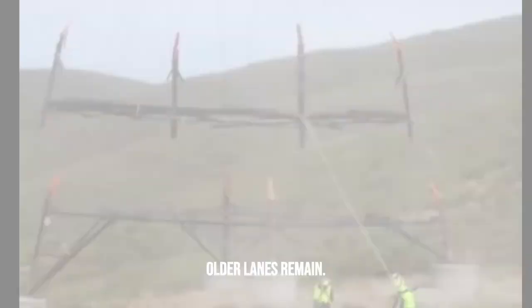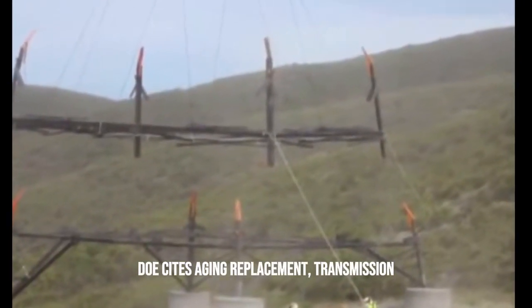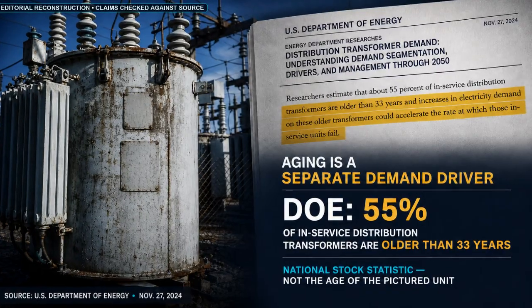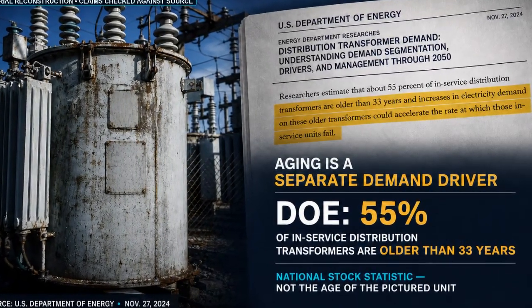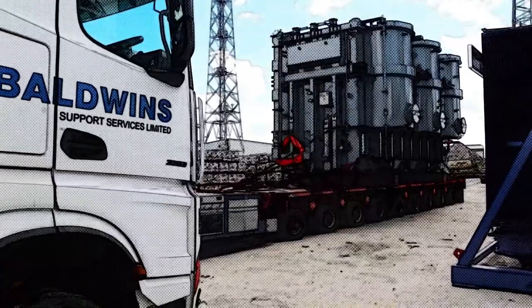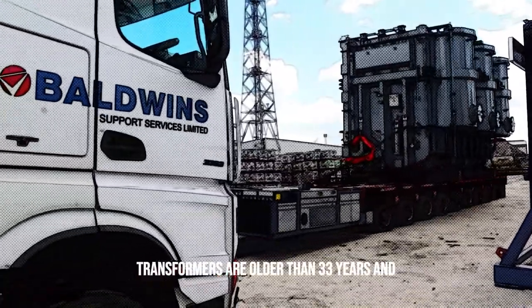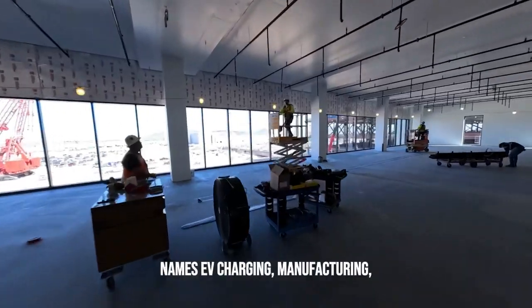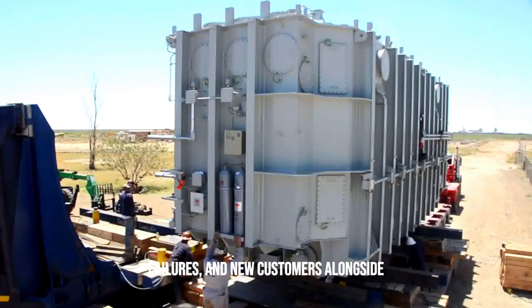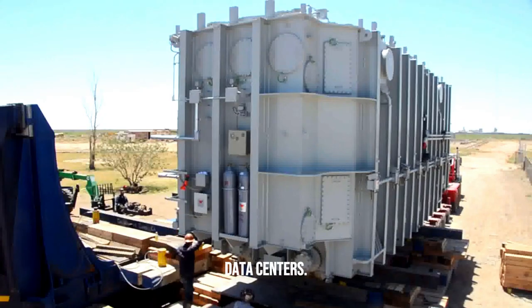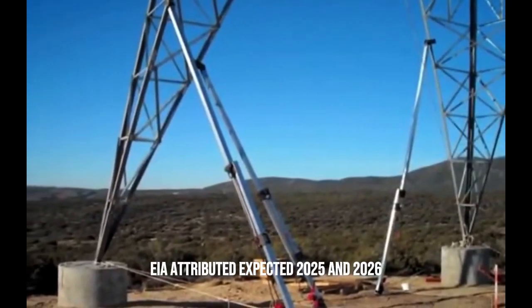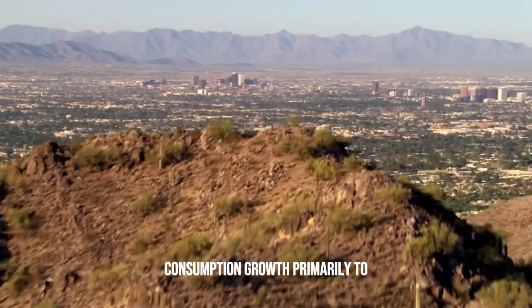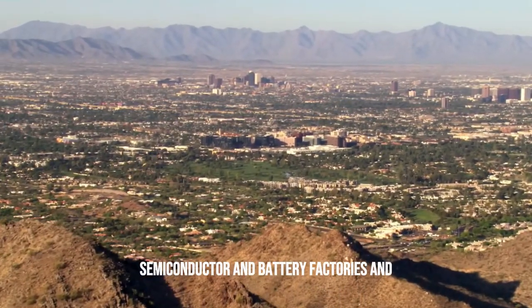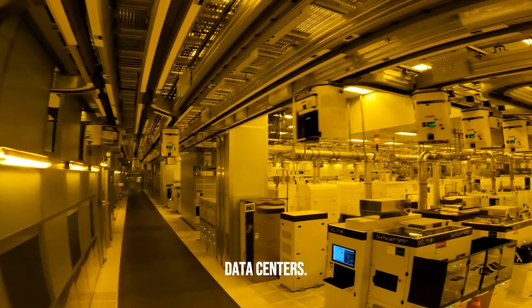Older lanes remain. DOE cites aging replacement, transmission expansion, renewable generation, and storage for large transformers. It reports 55% of distribution transformers are older than 33 years and names EV charging, manufacturing, failures, and new customers alongside data centers. EIA attributed expected 2025 and 2026 consumption growth primarily to semiconductor and battery factories and data centers. AI accelerates the collision. It did not create every demand lane.